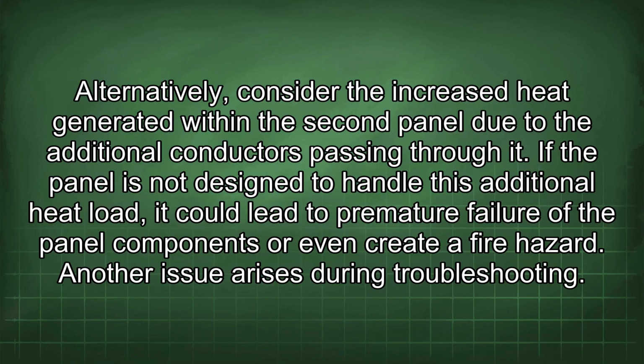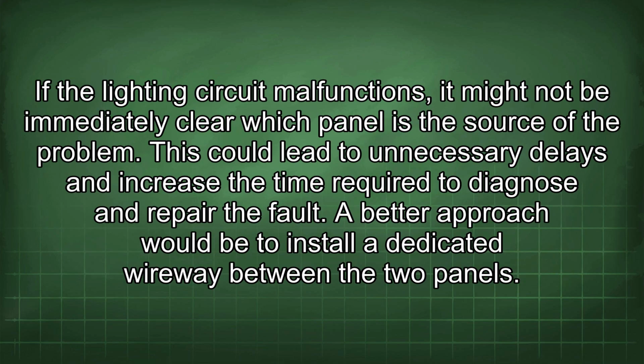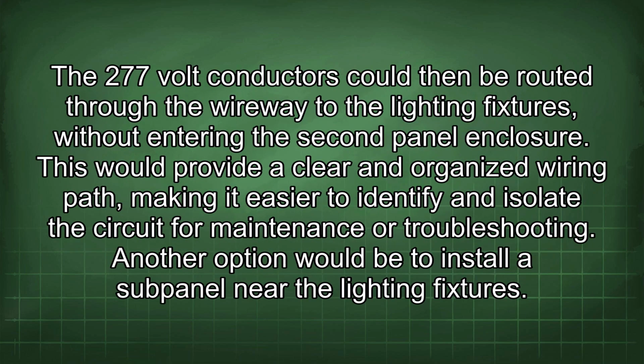Another issue arises during troubleshooting. If the lighting circuit malfunctions, it might not be immediately clear which panel is the source of the problem. This could lead to unnecessary delays and increase the time required to diagnose and repair a fault. A better approach would be to install a dedicated wireway between the two panels. The 277-volt conductors could then be routed through the wireway to the lighting fixtures without entering the second panel enclosure.